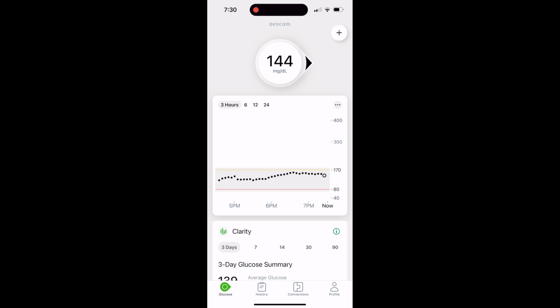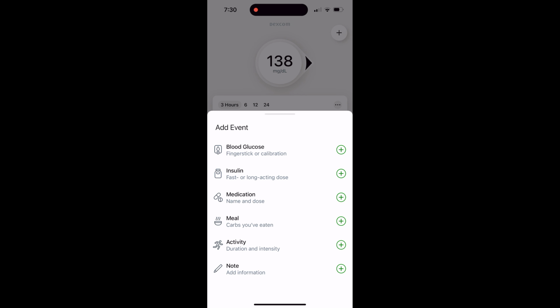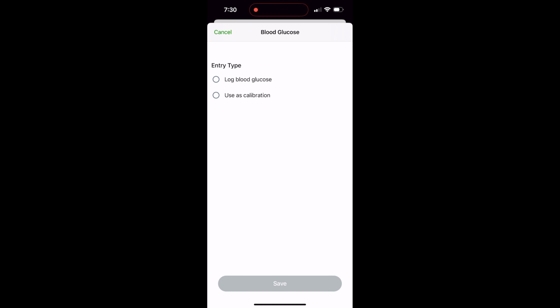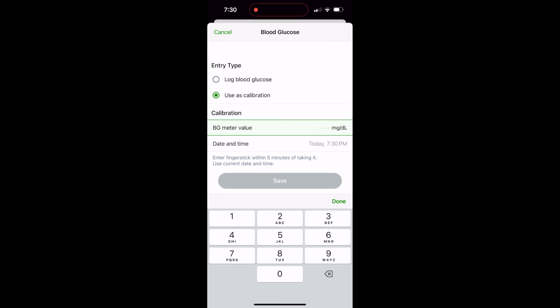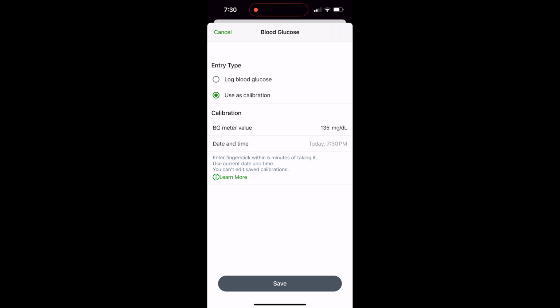And if they're off, here are the steps you need to follow. Click the plus sign in the upper right corner of your Dexcom app, then click on blood glucose, and you'll see right below it says finger stick or calibration. Click the plus sign to the right, then click use as calibration, and enter the number from your glucometer into the BG meter value space provided. You'll then get a message that says calibration saved, and this calibration will take effect on the next reading.